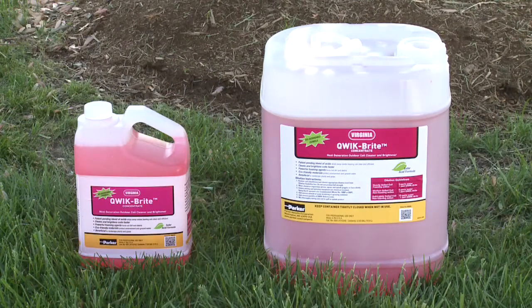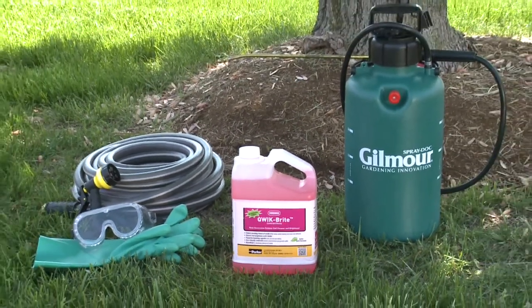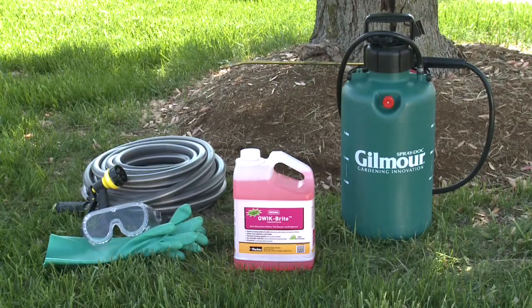QWIK-Brite is available in 1-gallon and 5-gallon containers. To clean an outdoor condenser coil with QWIK-Brite, you'll need a pump-up sprayer, a water hose, polyurethane gloves, and eye protection.